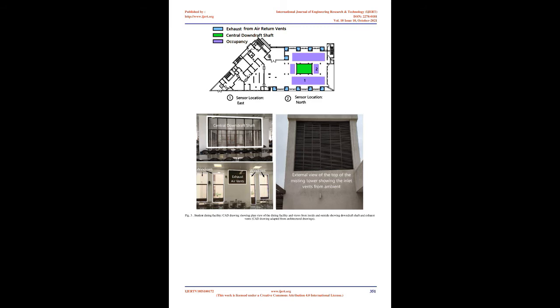In contrast, in the classroom complex, the space is more confined, approximately 62 sqm area per classroom. Students spend longer periods of time, 1 HR to 2 HRS, in the same classroom, and have higher expectations of thermal comfort. In addition, projection systems, monitors, computers, and other audiovisual systems installed in the classrooms are more sensitive to temperature and particularly to humidity. As a result, users were generally much less satisfied, as ascertained from informal surveys, and often complained of high humidity and wetness, and high noise levels from the PDEC fan.